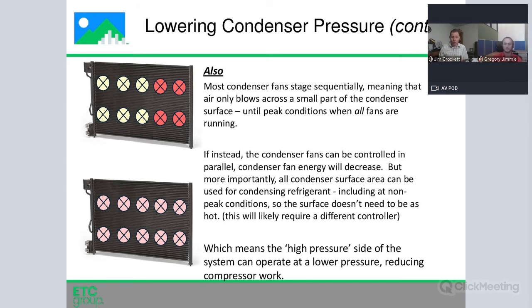One of them is, if you're familiar with the fan affinity laws, it takes a lot more energy to run a fan at 100% than it does at 50%, across the same path. In fact, it takes about 8 times as much energy to run at 100% than it does at 50%. The second problem, which was less obvious to me, is that you're only blowing air across, in this case, 40% of the coil. And so only 40% of your coil is being used for heat transfer.